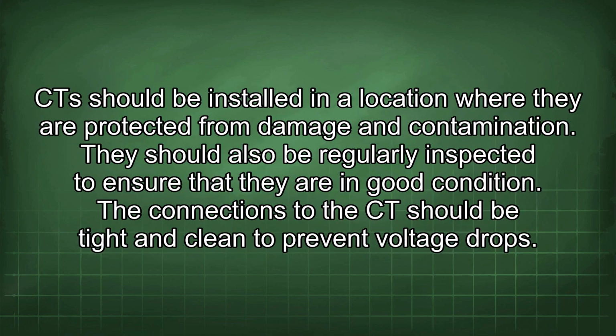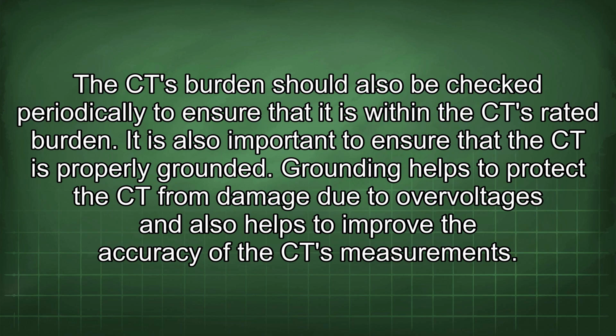CT should be installed in a location where they are protected from damage and contamination. They should also be regularly inspected to ensure that they are in good condition. The connections to the CT should be tight and clean to prevent voltage drops. The CT burden should also be checked periodically to ensure that it is within the CT rated burden.